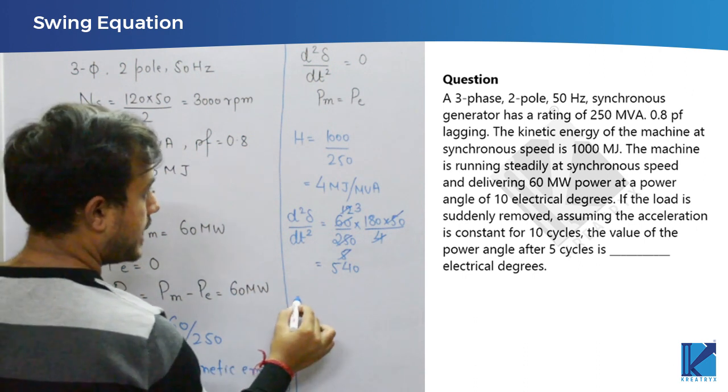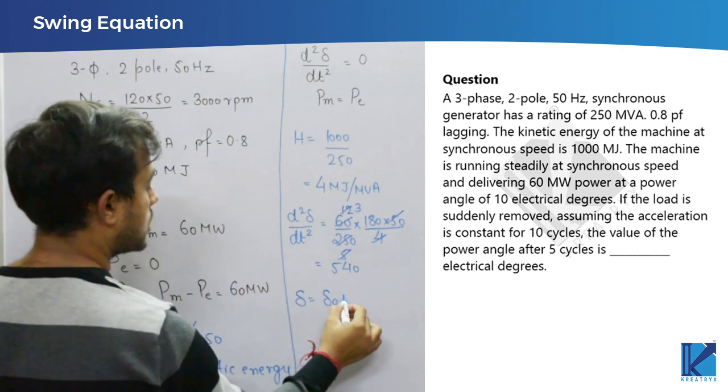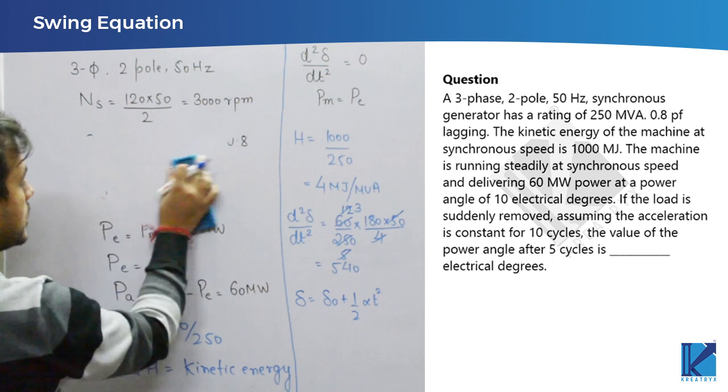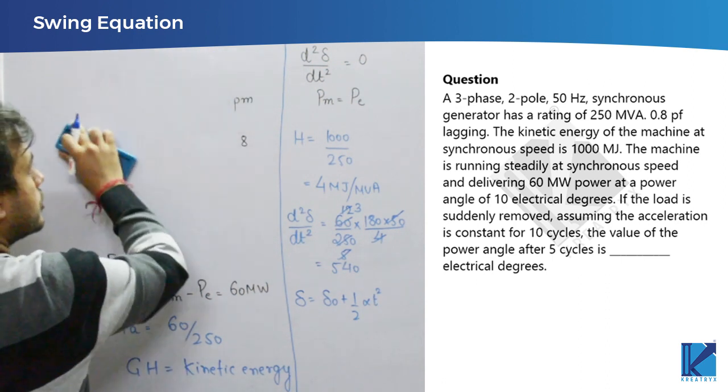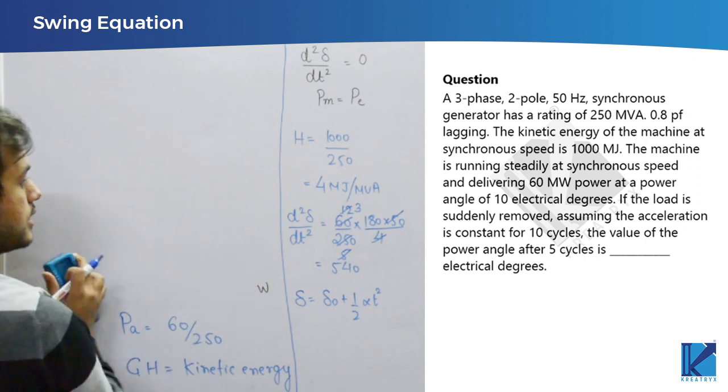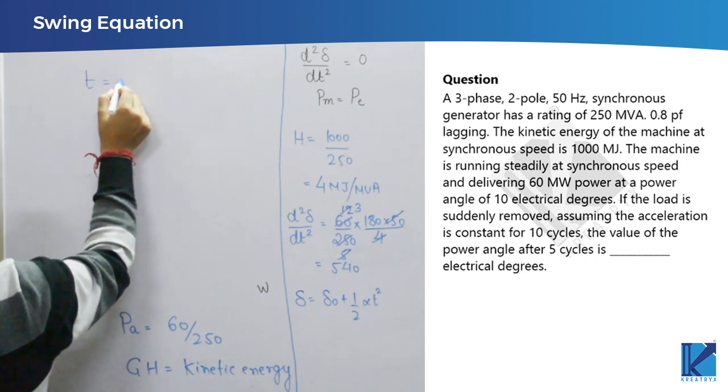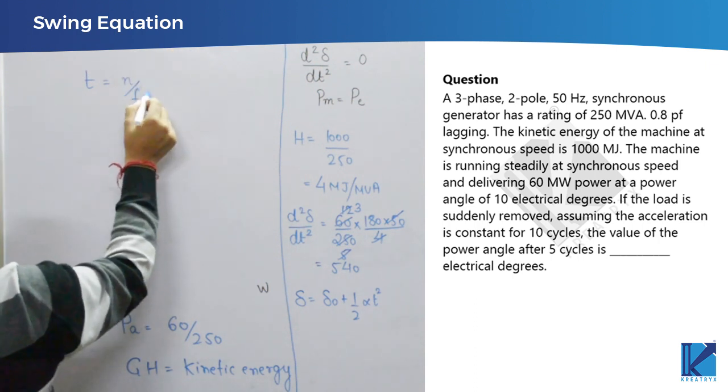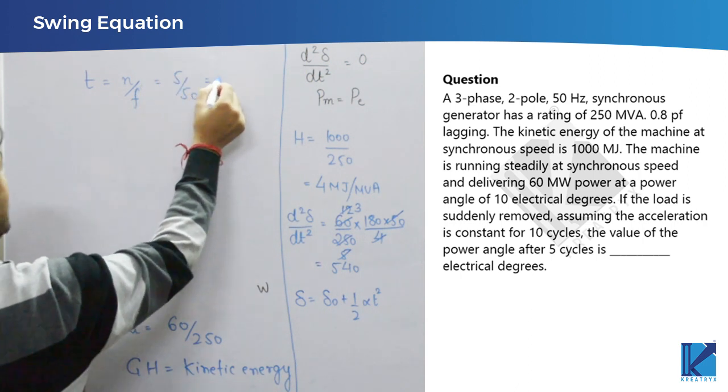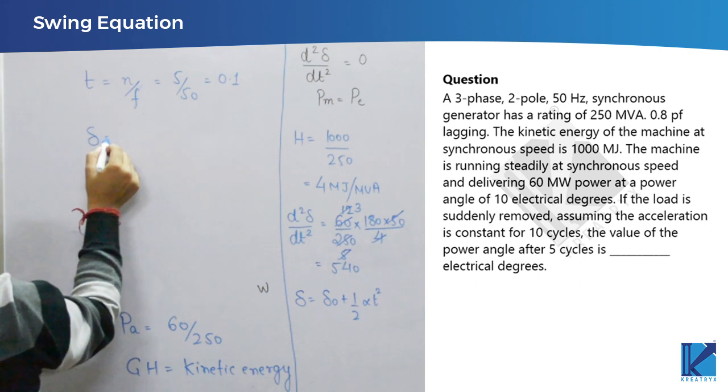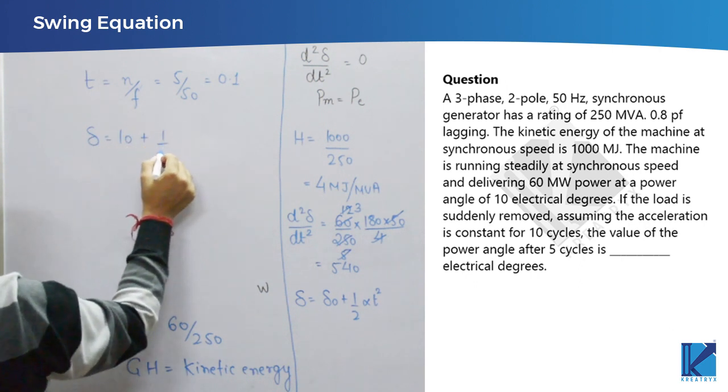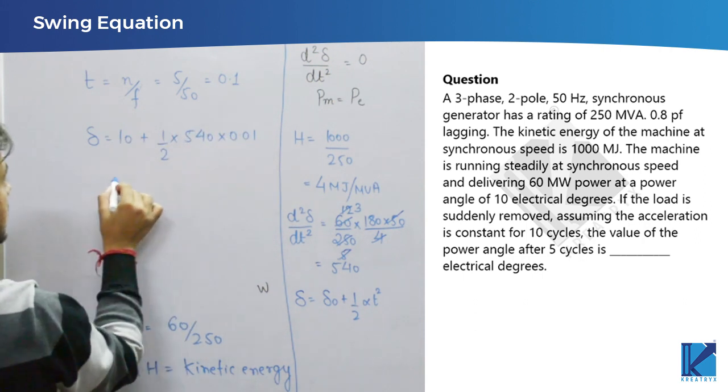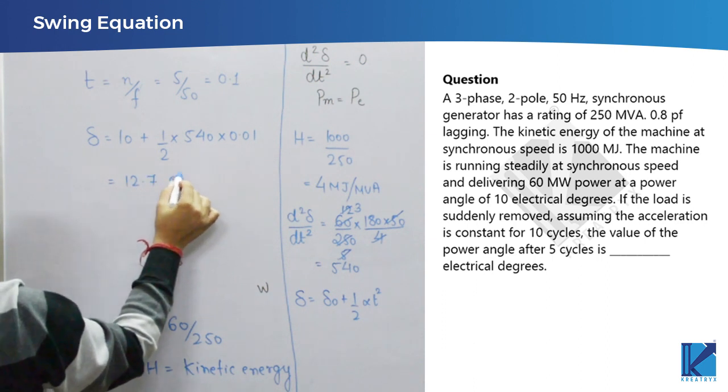Now, it is asking us after 5 cycles the value of delta. Delta is delta naught plus half alpha t square. So, for 5 cycle, we have to first find the time of 5 cycles. As I have told you the time of n cycle is n by f, so 5 by 50 that is 0.1. So, what will be the value of delta? 10 initial value was given as 10, plus half into 540 into 0.01, that is 12.7 electrical degree.